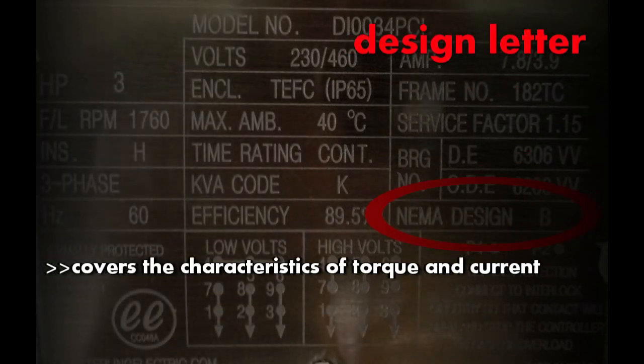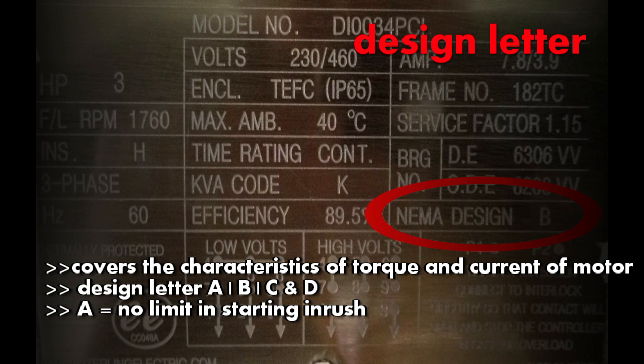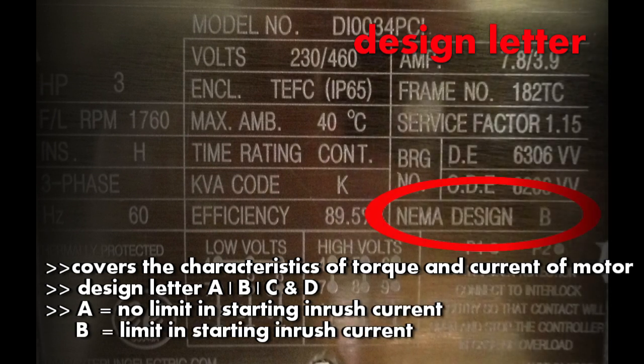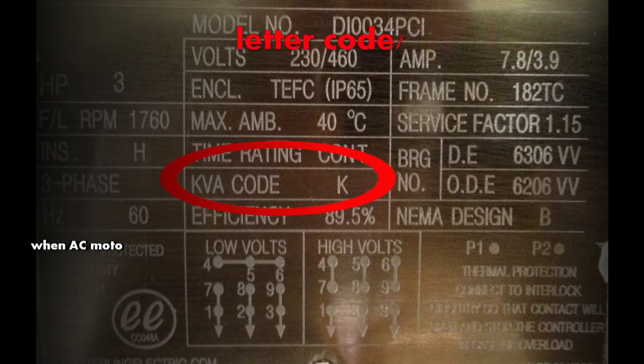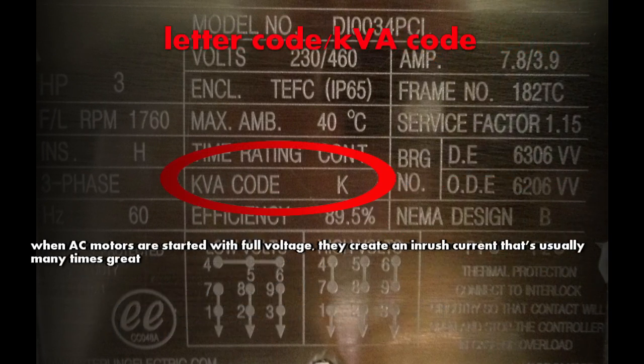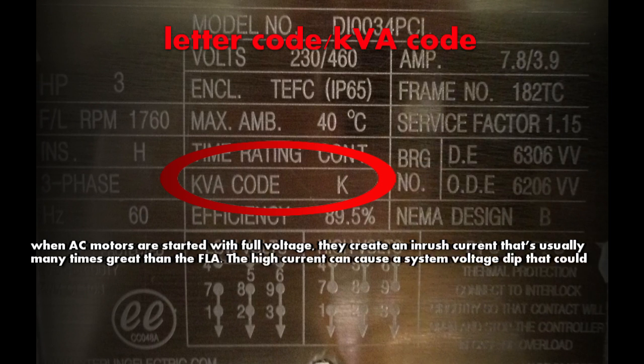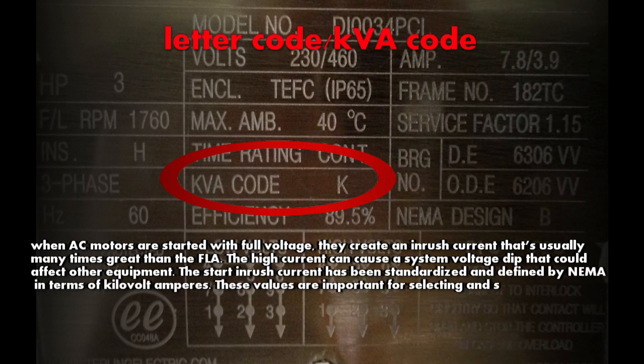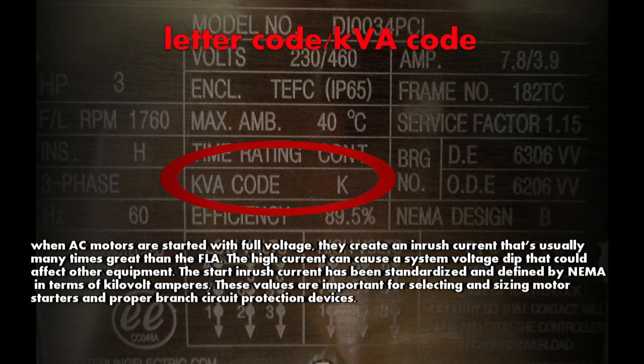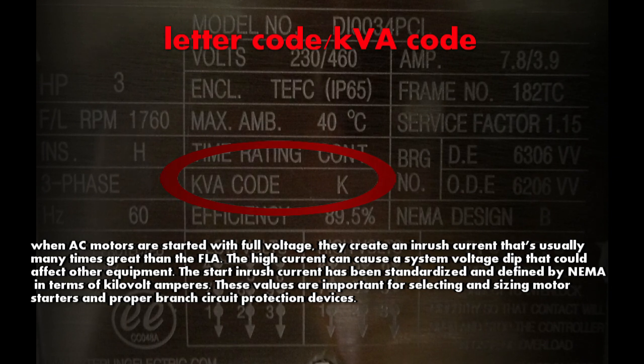Next is the design letter. It covers the torque and current characteristics of the motor. The categories A, B, C and D define different characteristics. Design A, there is no limit in starting inrush current. While in design B, the manufacturer puts a limit to inrush current on its product. When AC motors are started with full voltage, they create an inrush current that's usually many times greater than the full load ampere. The high current can cause a system voltage dip that could affect other equipment also. The start inrush current has been standardized and defined by NEMA in terms of kVA. These values are very important for selecting and sizing motor starters, proper branch circuit protection devices.